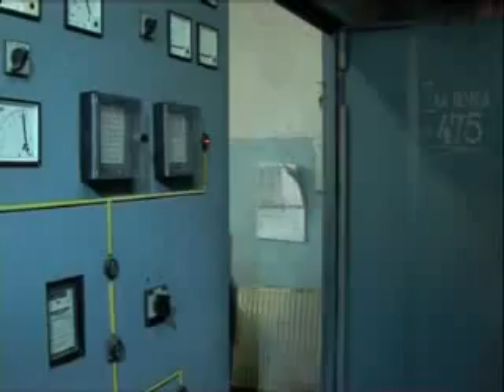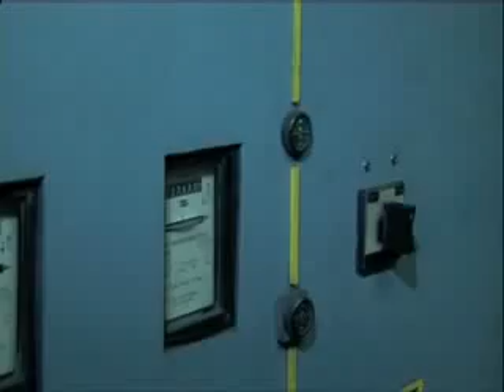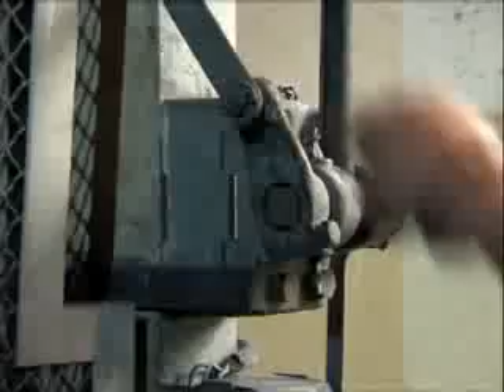Safely disconnecting the electricity supply, in practice: first, disconnection from the network, and labeling for identification. After disconnecting the primary side, the site is secured, and the secondary side is mechanically disconnected, an additional security measure against unauthorized reconnection.